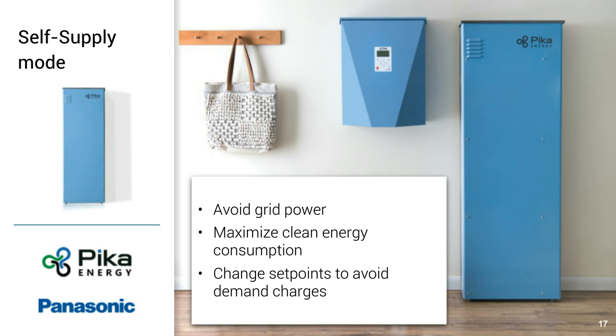So one example, if you have a customer who's in a commercial setting and they've got a demand charge that they are charged when they peak over a certain kilowatt limit for 15 minutes, then what you could do is set your inverter to watch that demand on the AC side, and as soon as they approach that threshold, it'll draw from the battery automatically, making sure that they're not going to peak over that limit. And while they're under a low power threshold, they can also charge from the grid to make sure their battery has the capacity that it needs. So this is a really, really powerful application for those customers, because just within a single 12-month period of avoiding those peaks, they could save thousands and thousands of dollars on their demand charges.